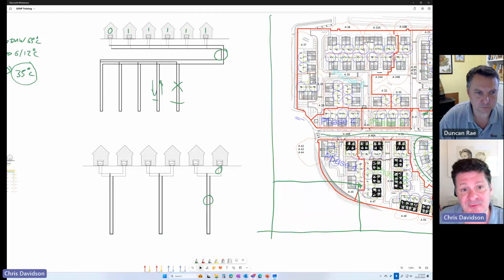So there are a number of different ways you can balance the flow. Commonly, you use manifolds, which have got adjusting valves on them. You can use restricted header locations. So perhaps a borehole that's further away will have bigger pipe to supply that header. One that's closer might have a smaller pipe to artificially increase the pressure drop. Rule of thumb is that you want no more than a 10% difference in flow rate between your individual boreholes. And there are, as I say, a number of different ways of achieving that.